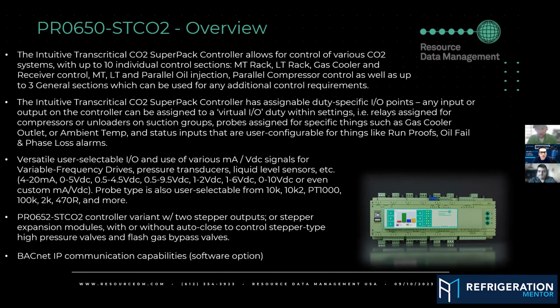Could you explain that a little bit just for everyone that's listening on that exact process? Because it's not only your control. I hear the exact same from other controller manufacturers. You want to just explain the process for that example there? Yeah, so run proofs for our controller, say your first compressor is on relay 1 and it turns on and runs, you then set up a status input for that controller saying this is the run proof for that compressor. If it doesn't return a closure, it's usually a closure, on that status input within a delay period, then depending on settings, it can lock that compressor out, or it will retry to restart the compressor several times. And then if it fails, it'll lock it out.